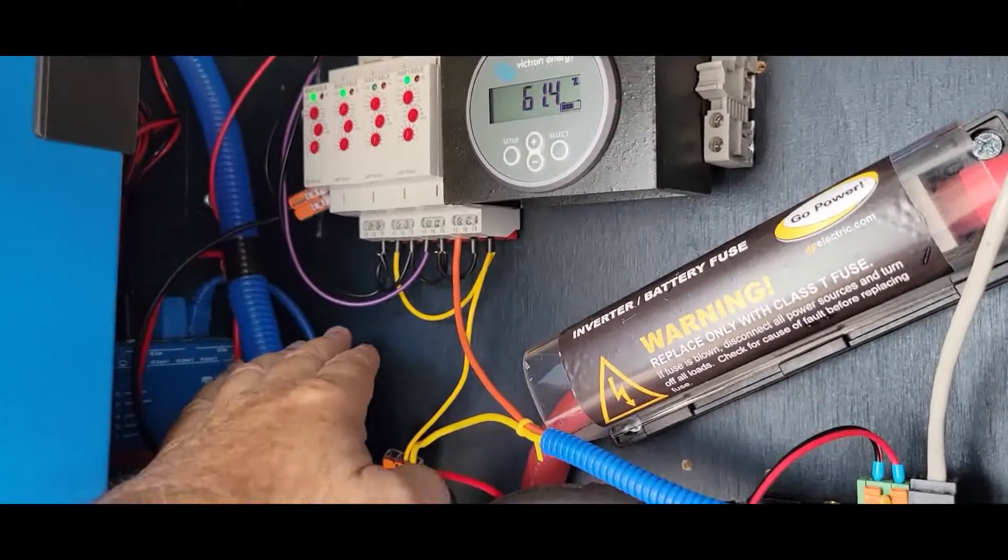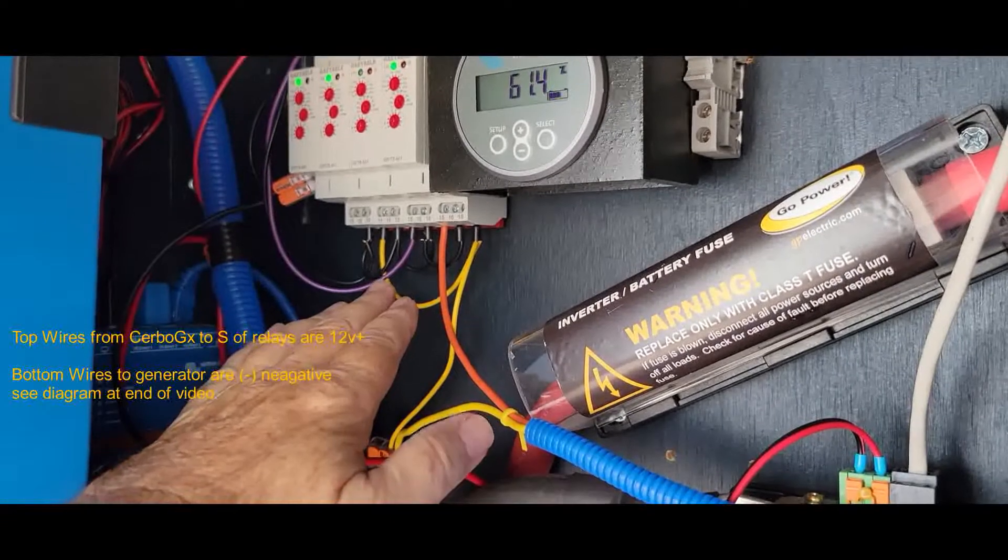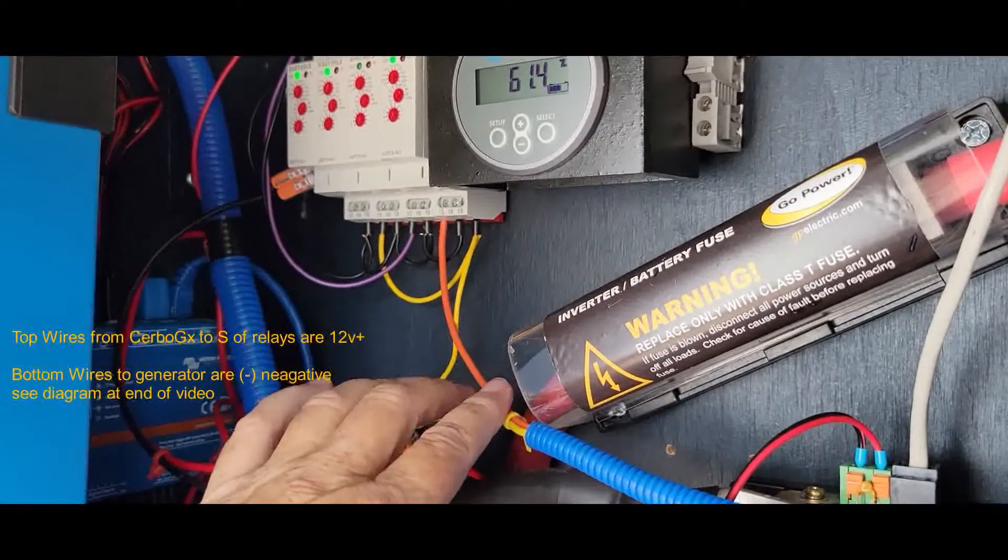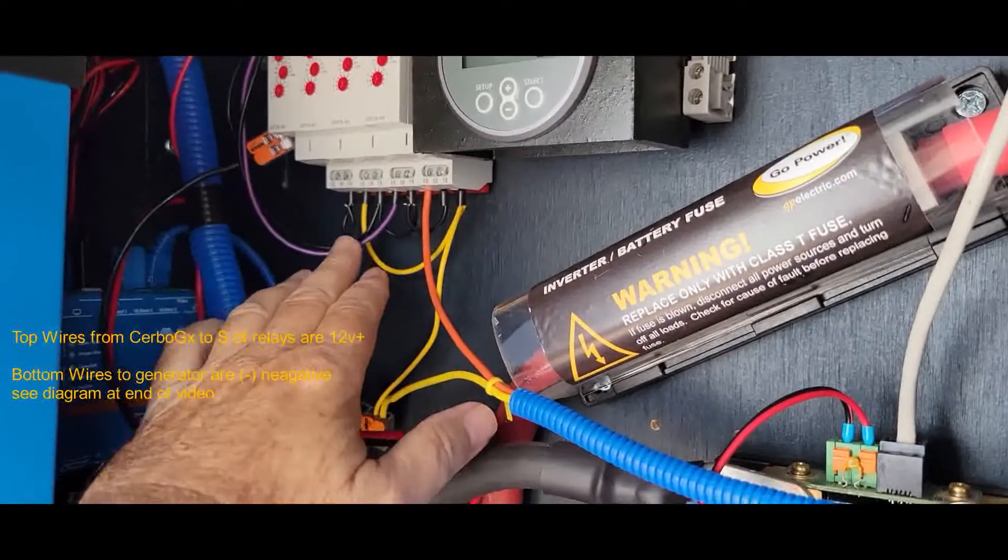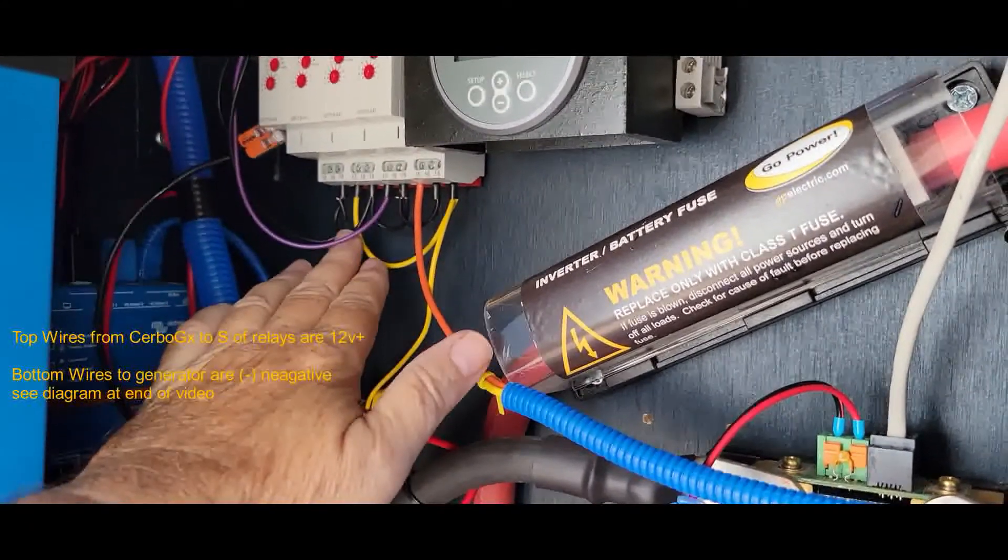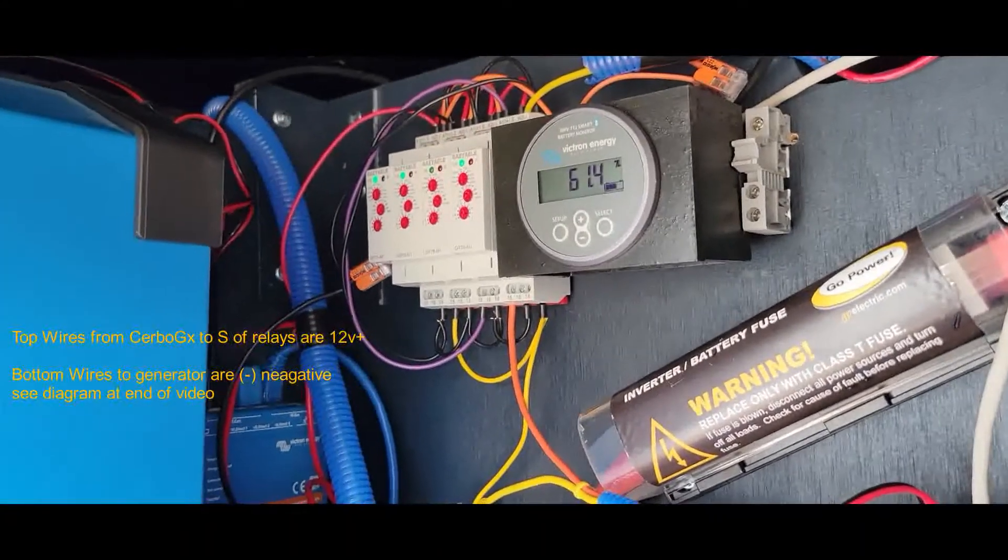And the source of the signal to the generator is a ground. And that's why these are black. These are coming from my ground bus bar, so it's ground. There's no 12 volt power going into the signal for the generator at all.